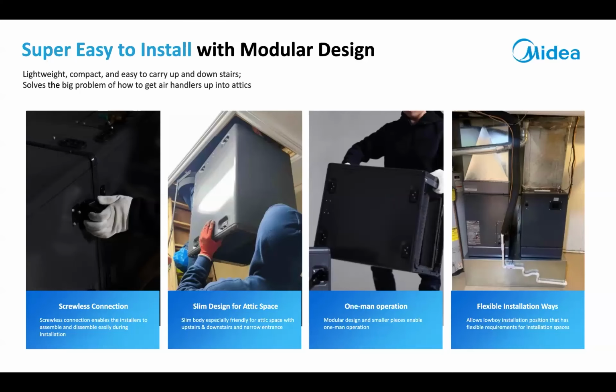Because I don't know how many of you have had to shove one of those full-size air handlers up through an attic hatch, but it's not easy. Ours, you can separate the modules and take the modules up one at a time, and then you just reassemble them in the attic. One man can carry one of the modules. And then we have, again, this is the low boy, we have flexible installations. It's very flexible.